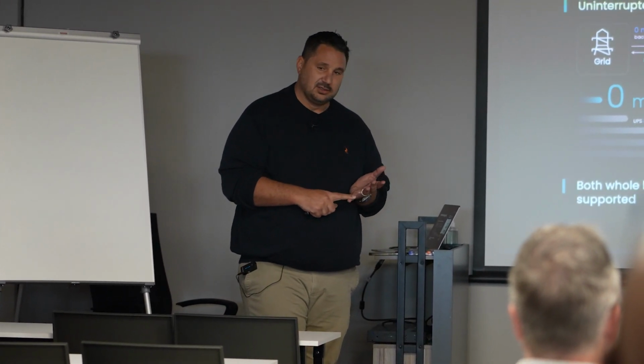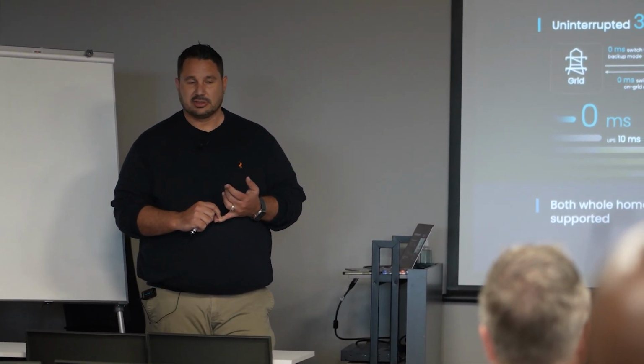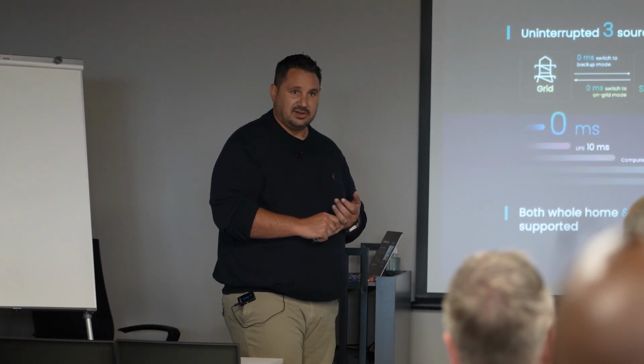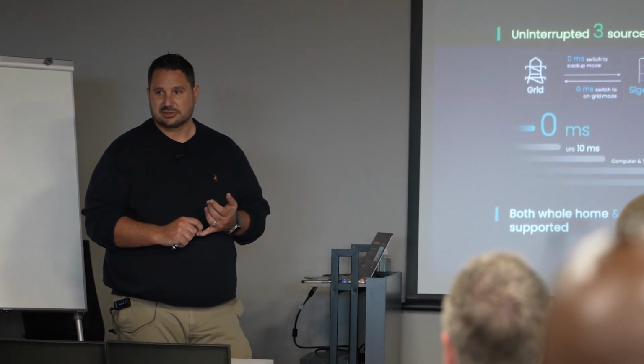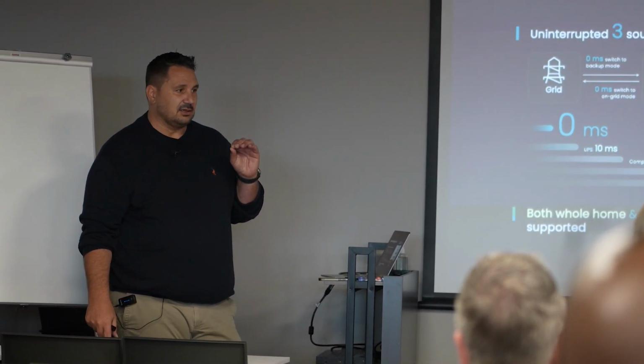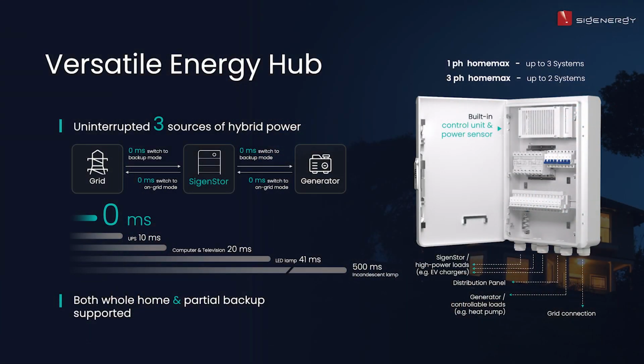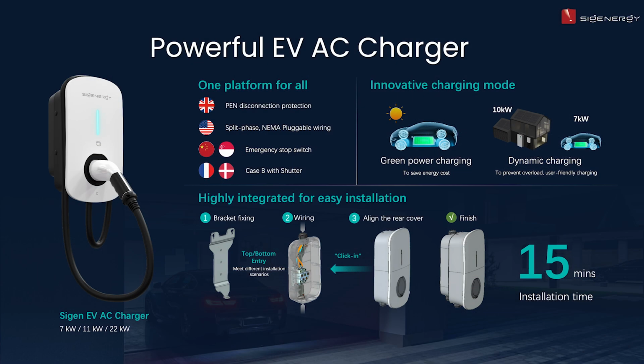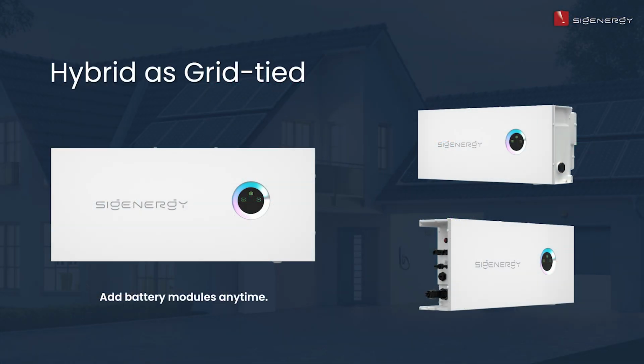So you know what a production line does with even 20 milliseconds. VSDs do not like any interruptions. There's a lot of things that do not have it. With 0 milliseconds, it's as good as true online UPS, which means you can run data centers and medical equipment on it as well. All right, then they've got an AC EV charger, which is just an additional product to this site. If you do not want to use a DC one, you can use an AC EV charger.